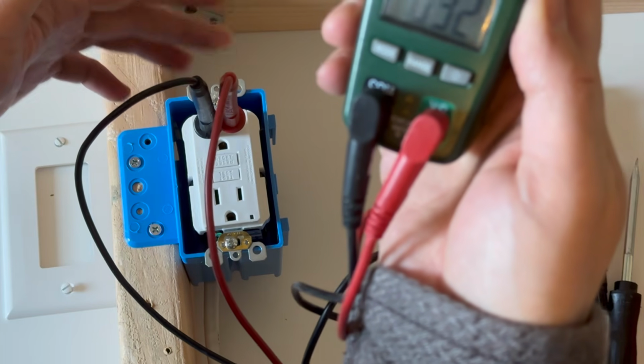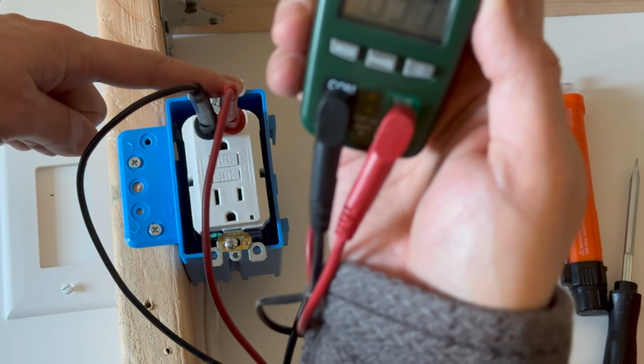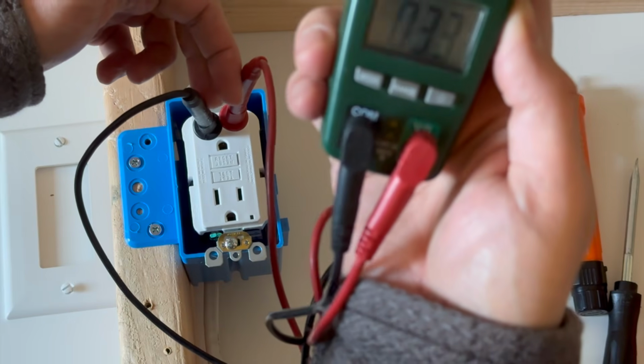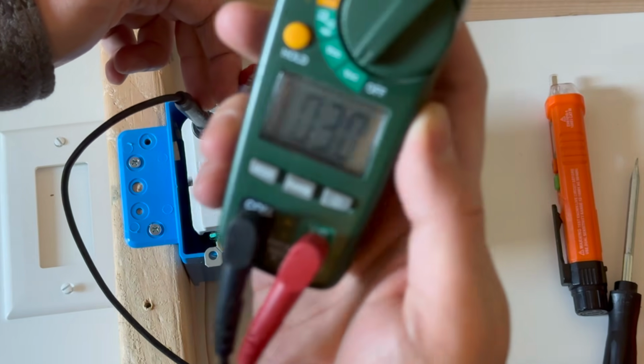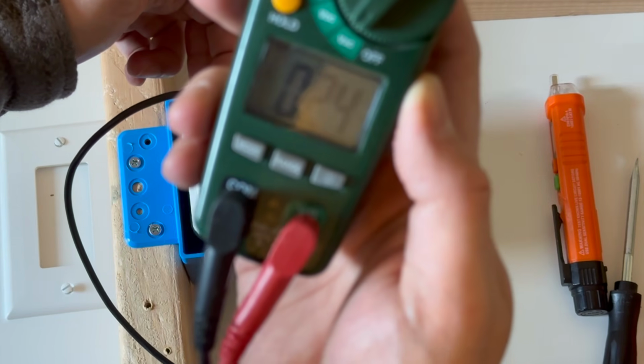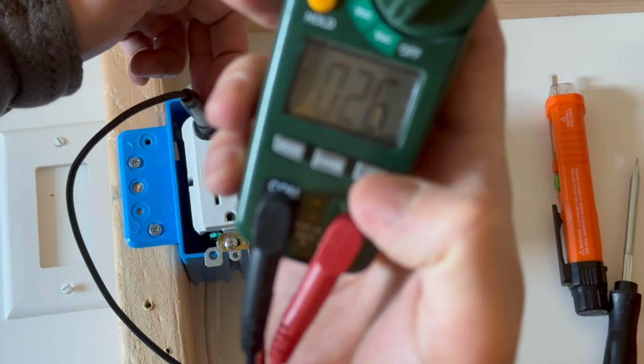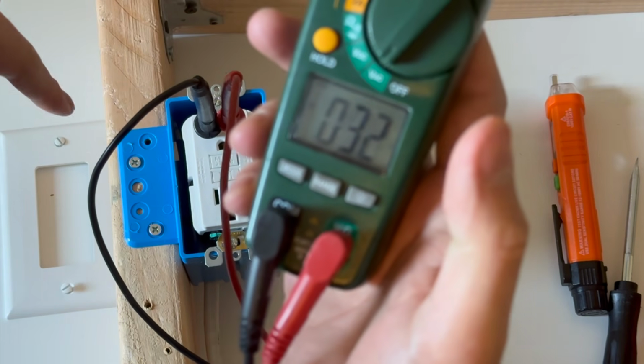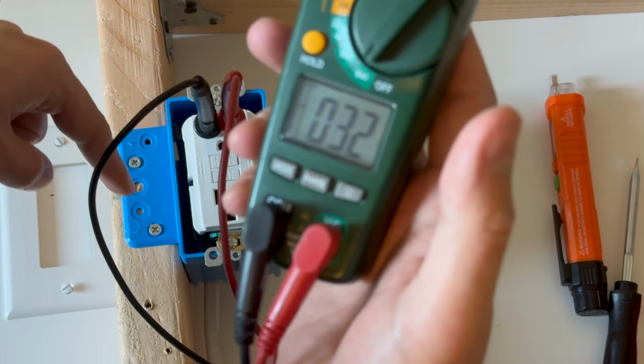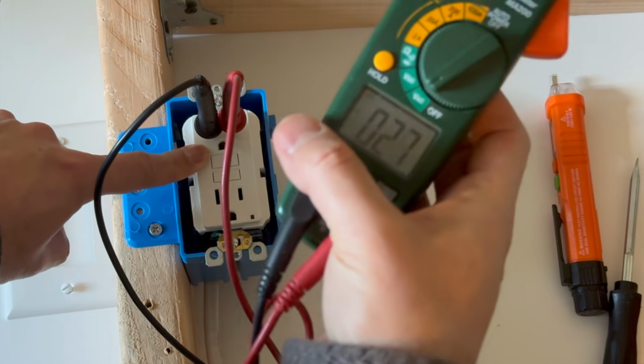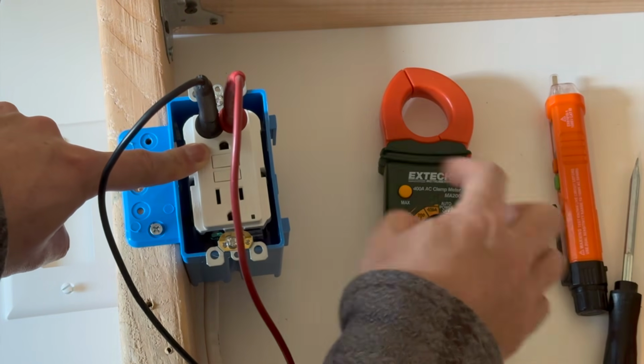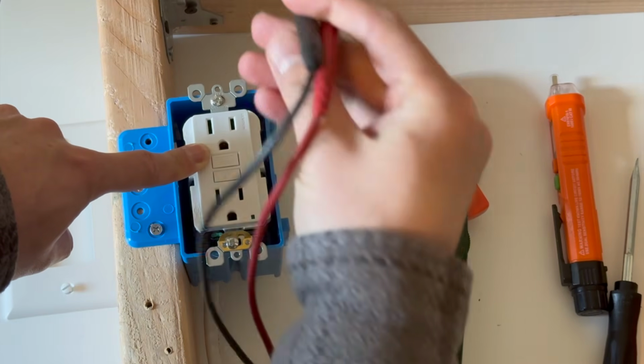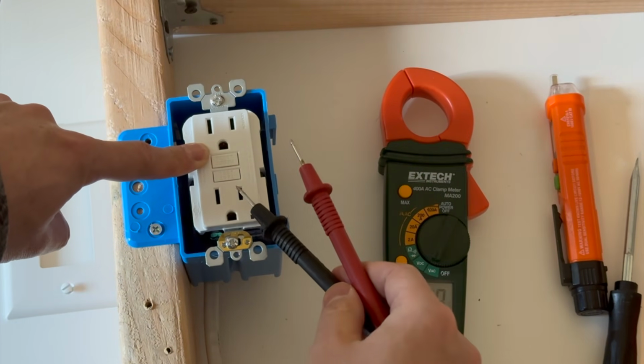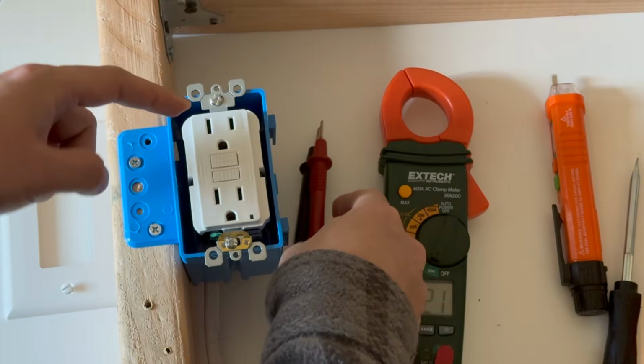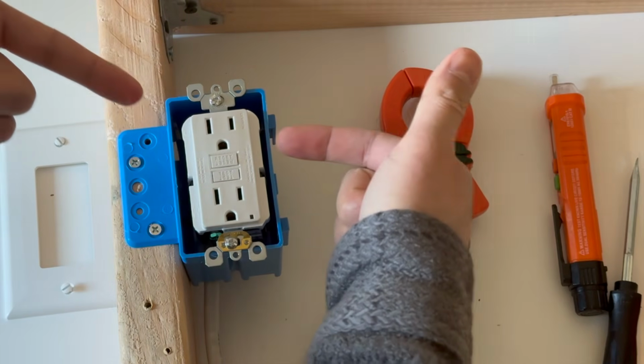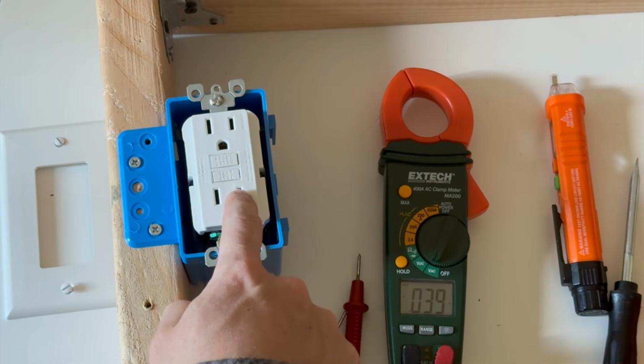So that's why a lot of people use it with one of their hands, and I try to read it like this to see if I have any voltage. So if I have anything like this, 0 essentially, that means I want to read the wires themselves, because these GFCIs can be reset only when it has a power, but sometimes they go out and you're not able to tell without removing and reading the terminals of the outlets. So that's what we're gonna do.